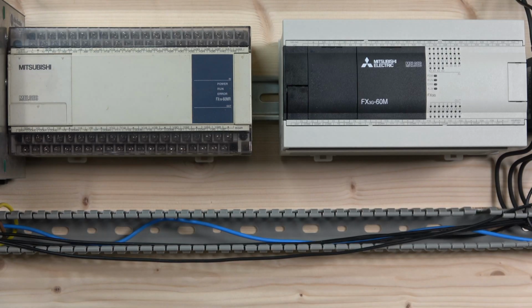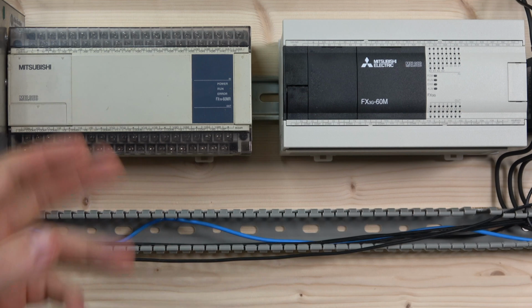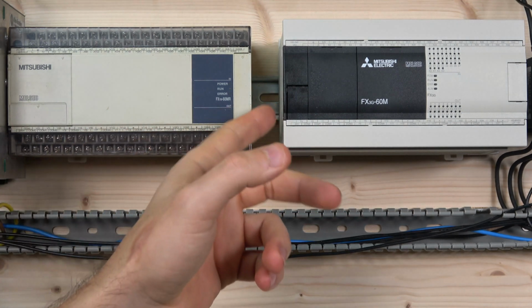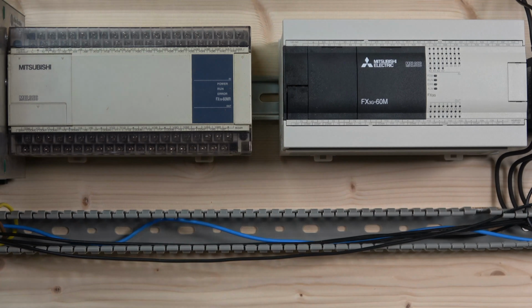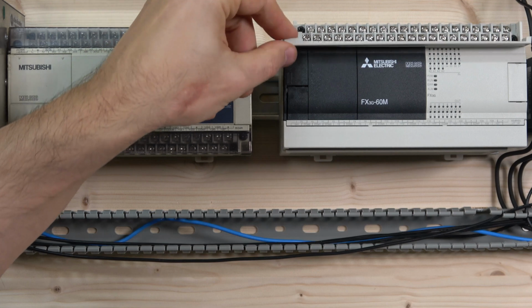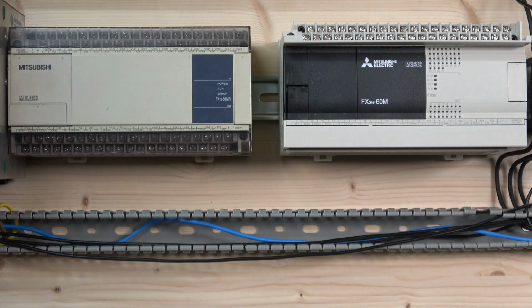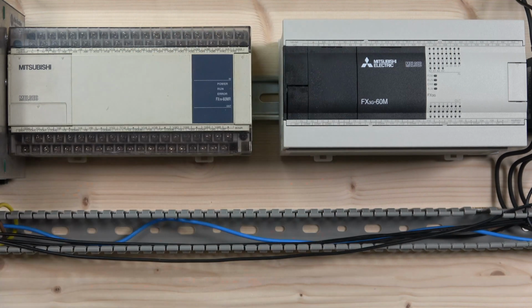Here we go. So here are both PLCs standing side by side. There is not much of a difference in the PLCs themselves. The only difference between the FX3G and the FX1N is a difference in height. That's something to look out for, because I have had one machine that was so tight with the cables where the PLC needed to be changed that I had to redo all the cables, because there was just not enough room to achieve the height. But that is in very, very rare occasions.